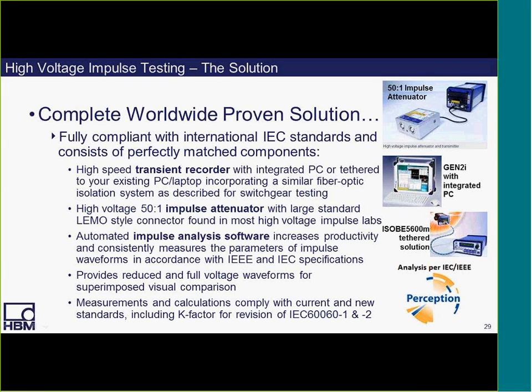So on the right, you can see the Gen 2i with an integrated PC, or you can use your own PC tethered to, just below that, the ISOBE5600m, which is a tethered solution that provides the ability to do impulse testing. The next item down, the high voltage 50 to 1 impulse attenuator, is used with large standard LEMO style connectors, which are found in most high voltage impulse labs. And there's a picture of that in the top right corner of the slide. That's the 50 to 1 impulse attenuator connected in turn to the isolated fiber optic transmitter.